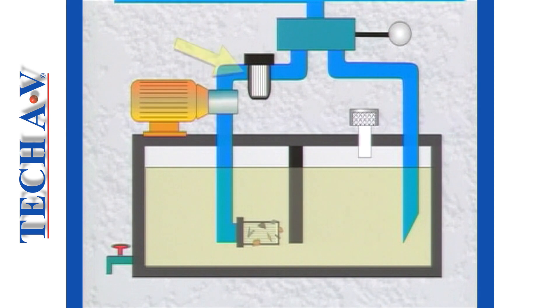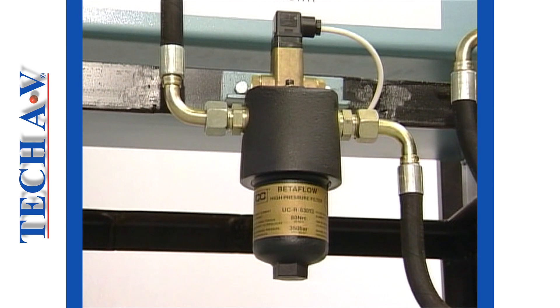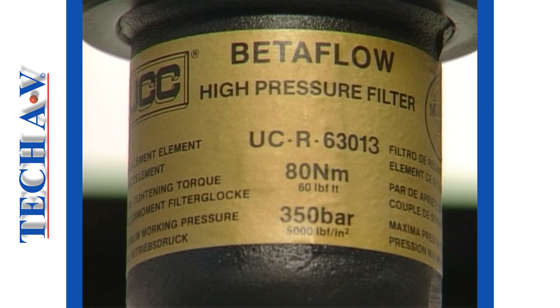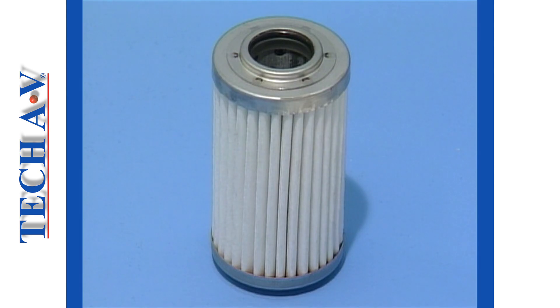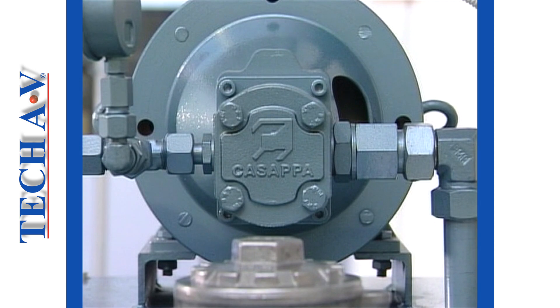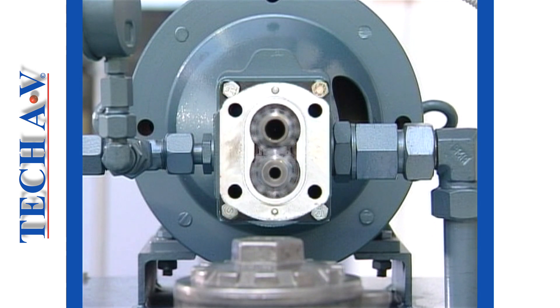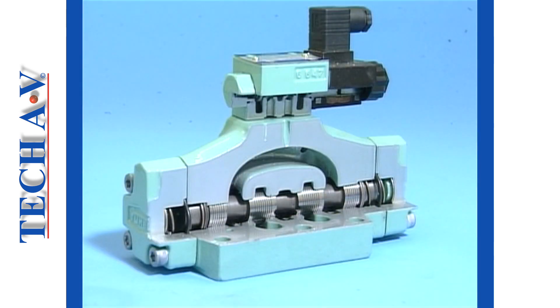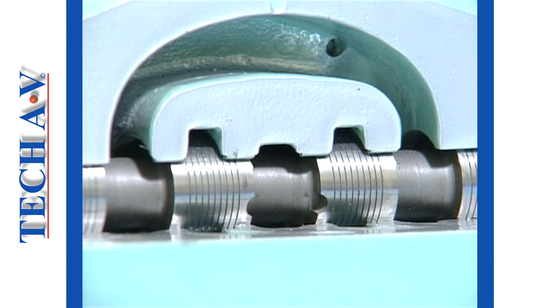The next device we come to is a pressure-line filter. This is normally a full-flow type filter, capable of withstanding high pressure. Pressure-line filters are designed to trap particles ranging in size from 3 to 40 microns. Such particles are often caused by abrasion within the pump and are particularly harmful to control valves and other devices that have very small working clearances.